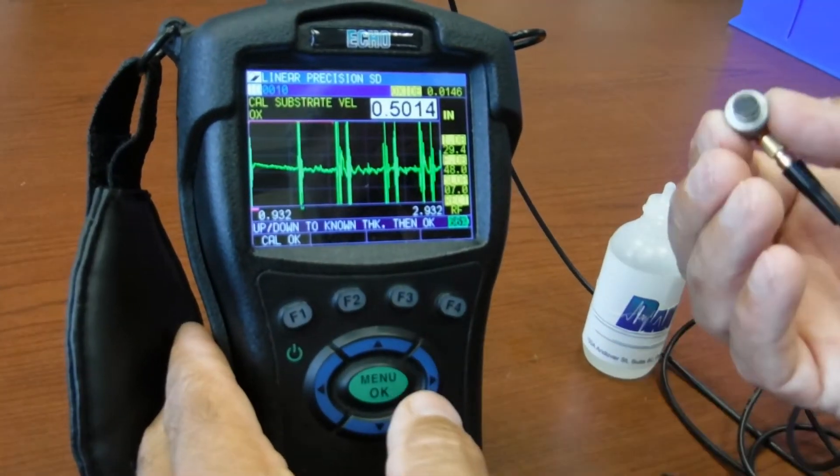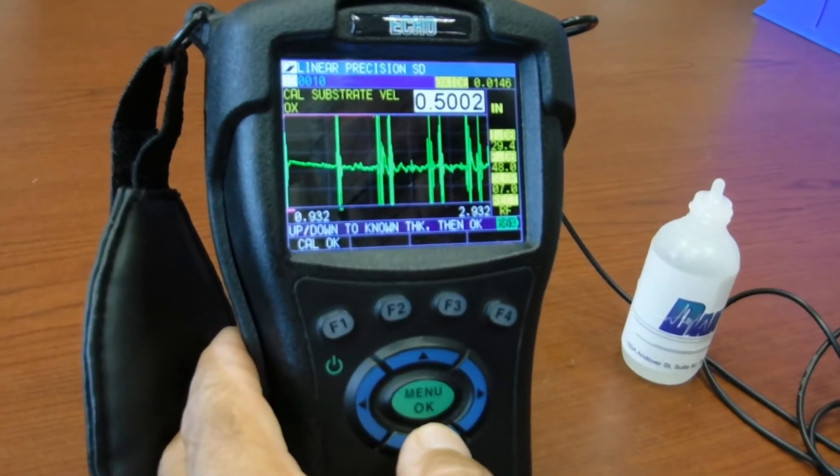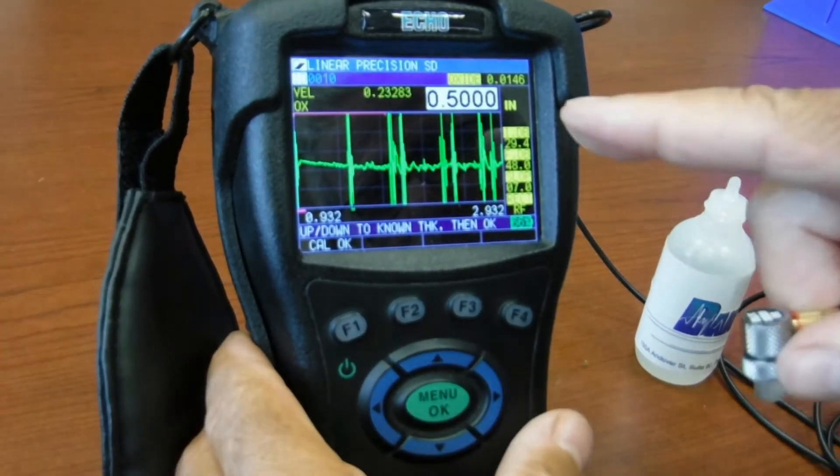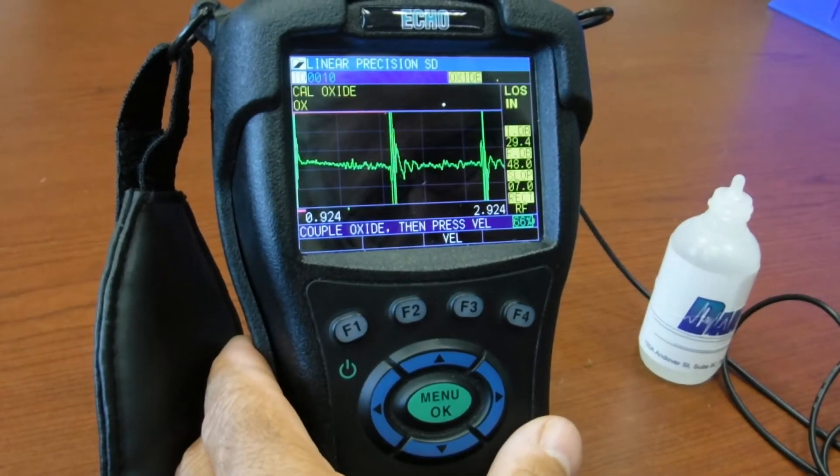It says couple to the thick which I'm on 500 thousandths. I press the F3 VEL key. You can remove the probe at that point. Scroll down to the known thickness of 500 thousandths and press menu OK. And it spits out the sound velocity for the carbon steel test block.